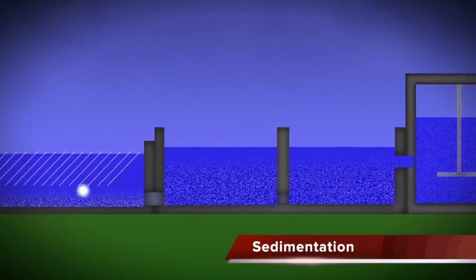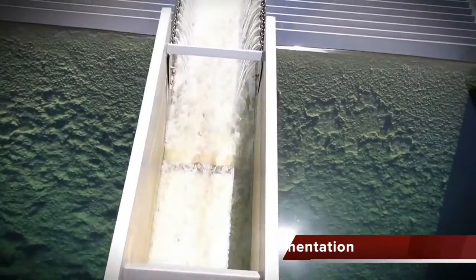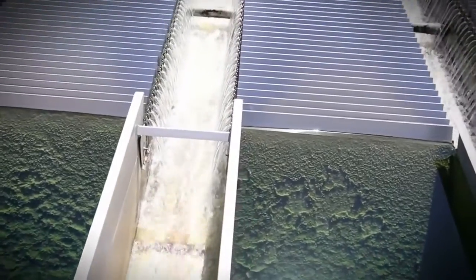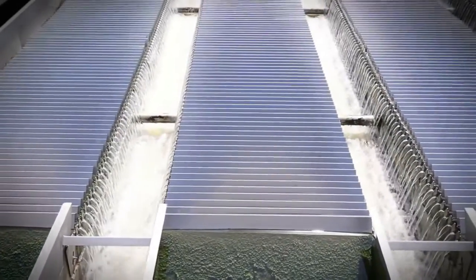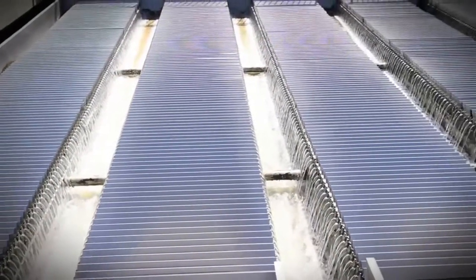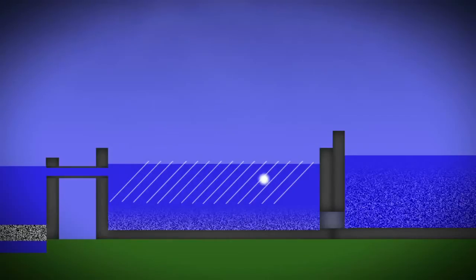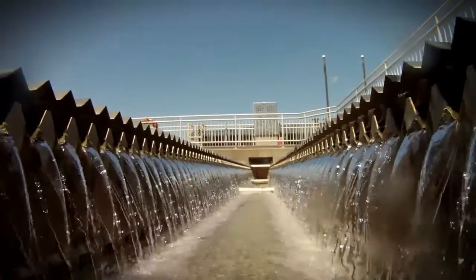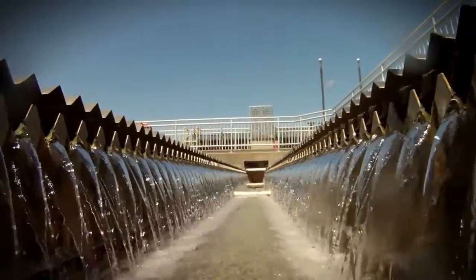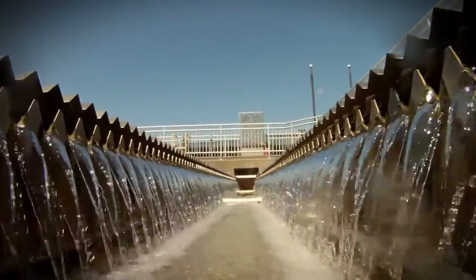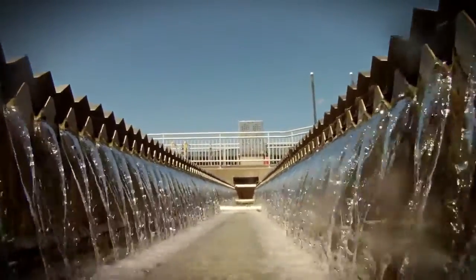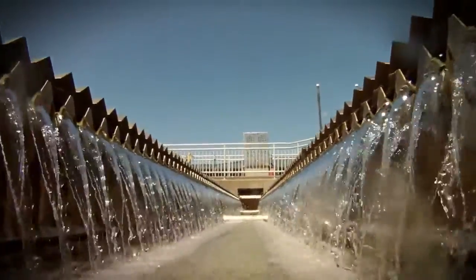After flocculation, the water together with the agglomerated particles flows through a huge sedimentation basin, where the liquid is split from the solid. The water flows very gently through the basin, and the settled particles at the bottom are collected by spinning scrapers into a hopper. A sufficient retention period is essential for the sedimentation process to complete. Then the clear water moves out of the basin to the filters.